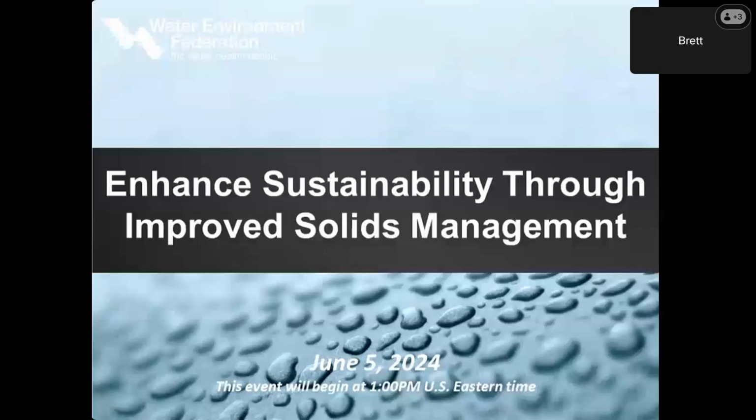Okay, and as we're waiting for that response to come in, what would a typical dosage rate be prior to the dewatering centrifuges? Brad, the answer there is it's typically between 2 and 3 gallons per 1,000 gallons of feed sludge flow.